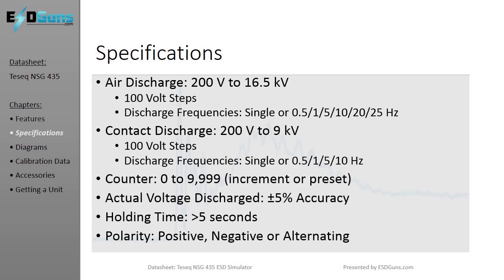Voltage capabilities exceed that required per IEC 61000-4-2 and other compliance standards for commercial electronics. In contact mode, frequencies from 10 discharges per second to 1 discharge every 2 seconds can be achieved. In air mode, speeds up to 25 discharges per second can be reached. During every test sequence, the default counter will increment on every successful discharge. The preset counter can be used to ensure a predetermined discharge count up to 9,999, counting backwards, terminating the test sequence when the counter reaches 0.